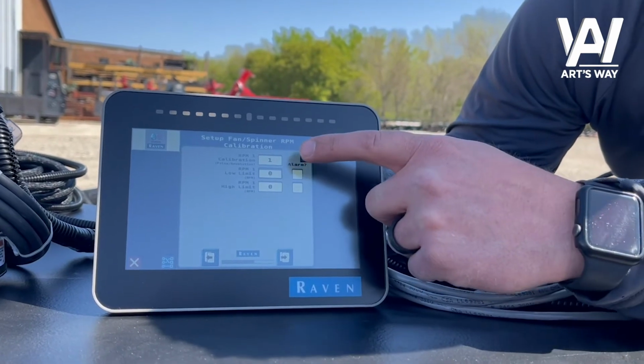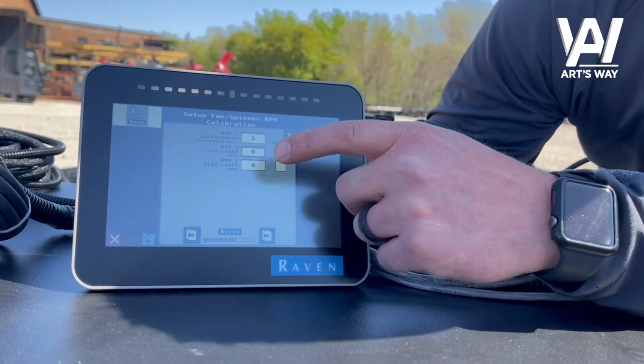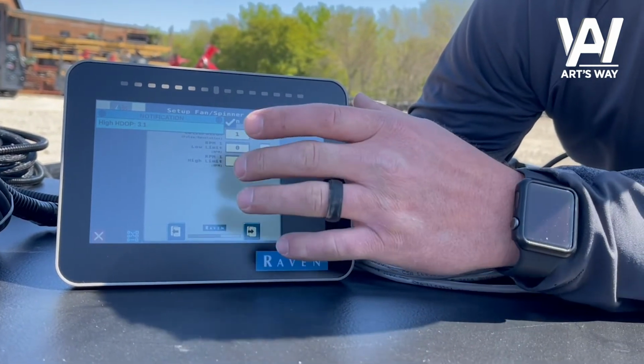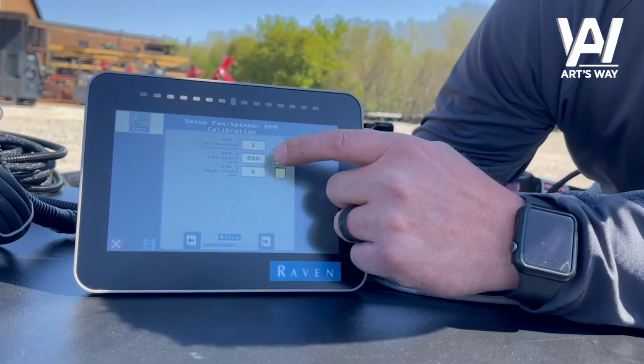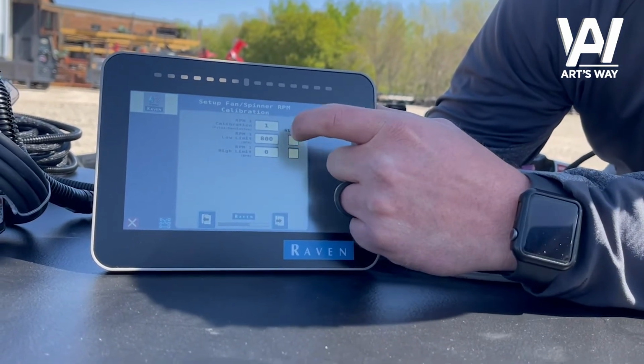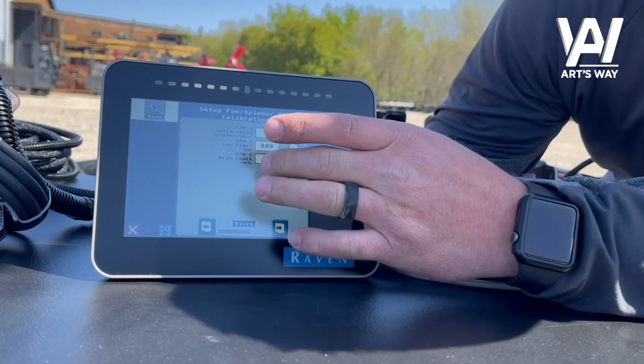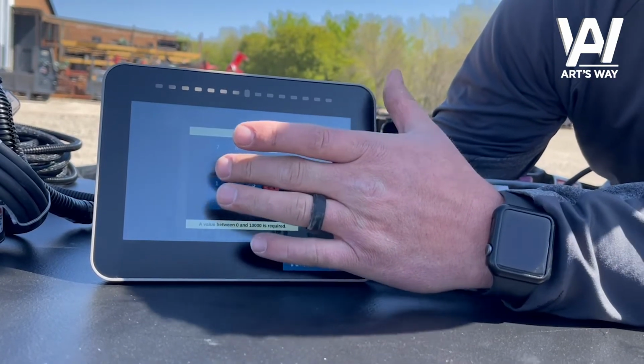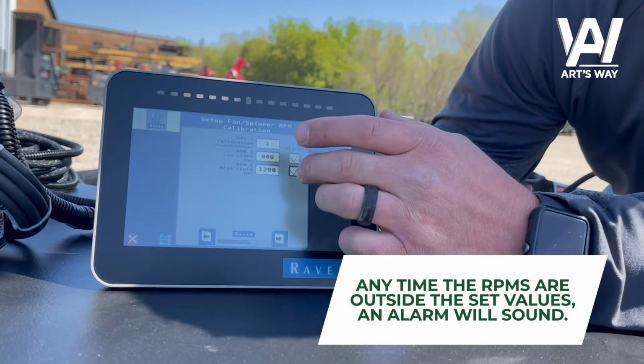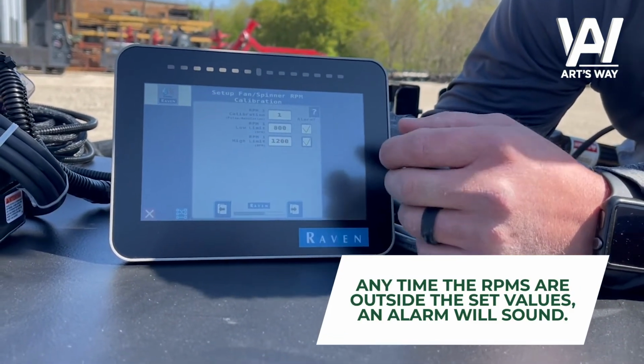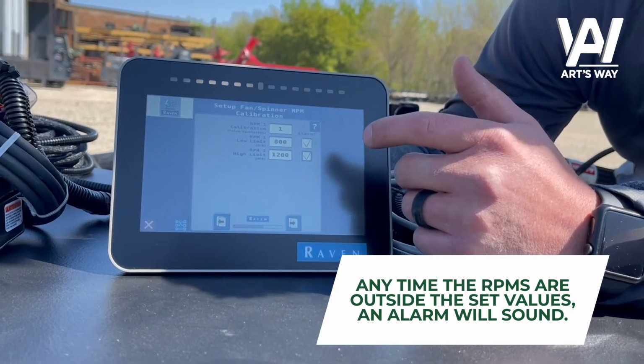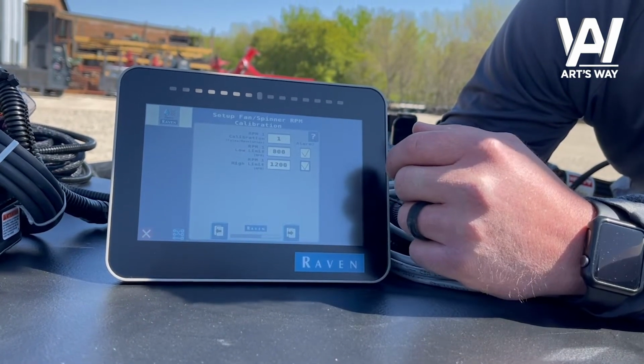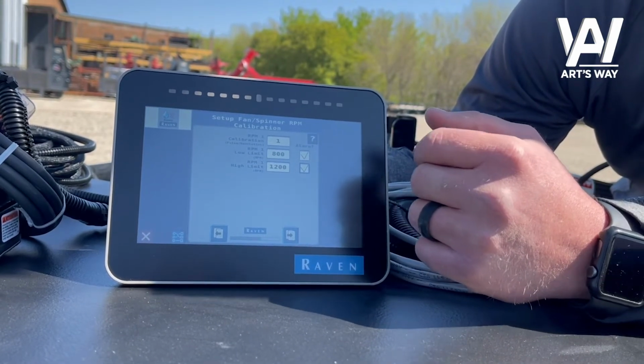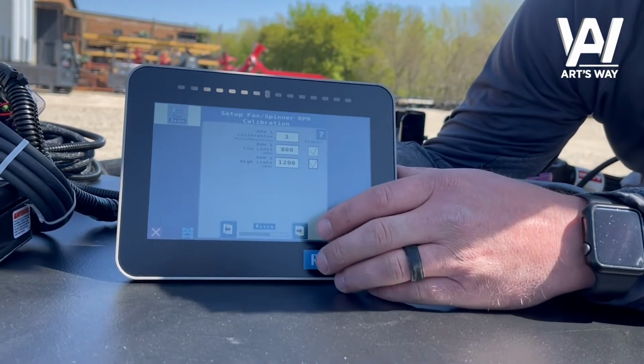So here we'll enter 1 for our RPM 1 calibration. Our low RPM limit we're going to set to 800, and we are going to check the box to alarm. Our high limit for our RPM, we're going to set to 1200, and we're also going to set that to alarm. So anytime the RPM reading gets outside of that set range, you will receive an on-screen alarm, just indicating that the shaft rotation has fallen below or above the set values.